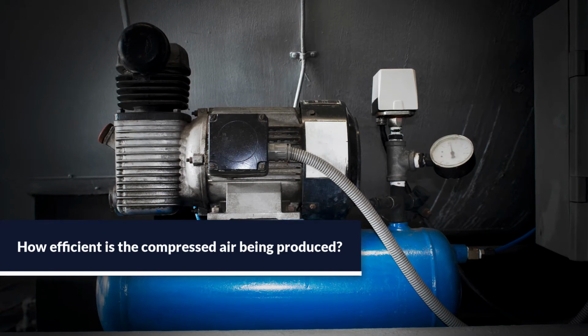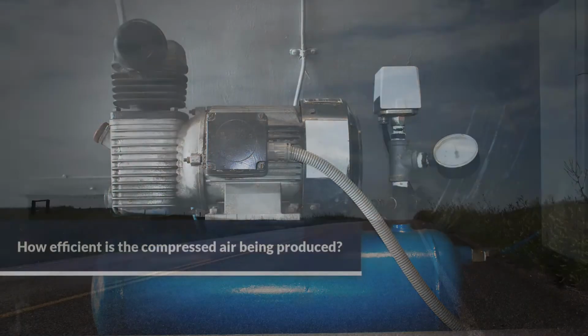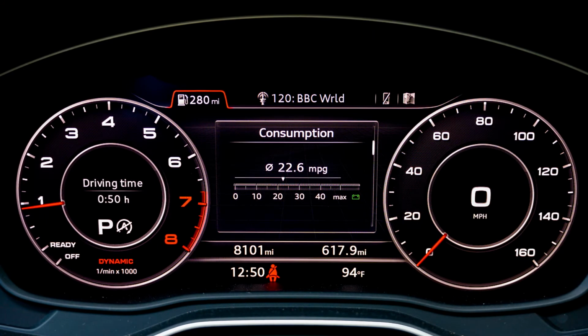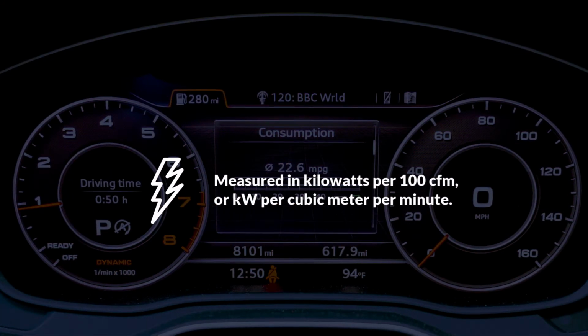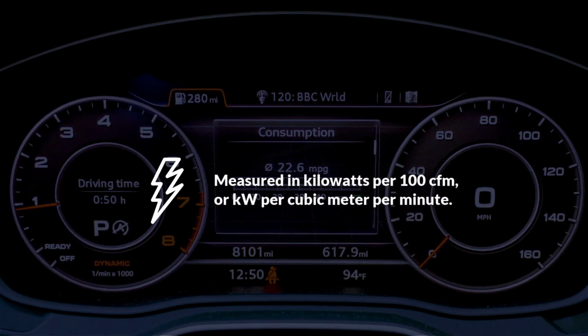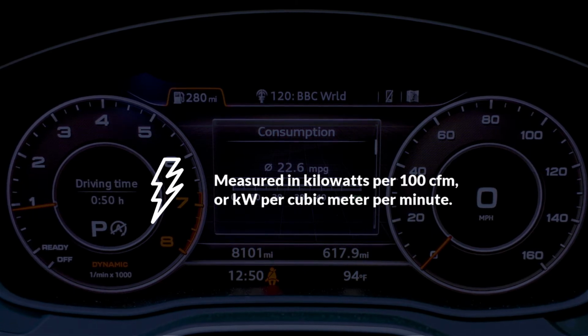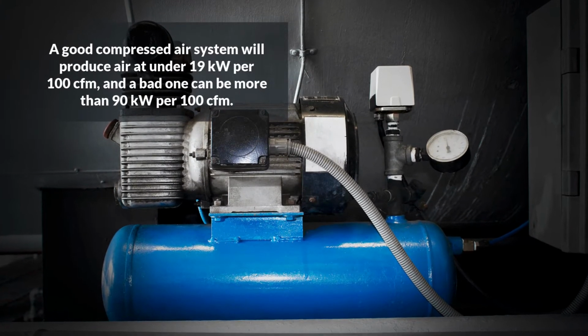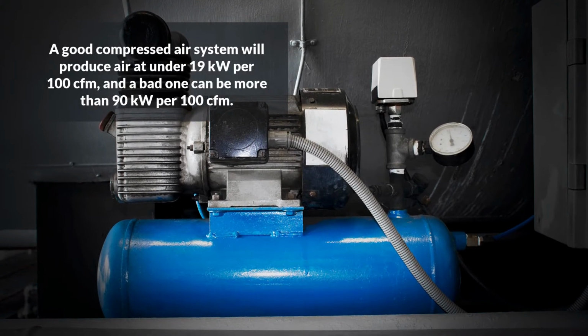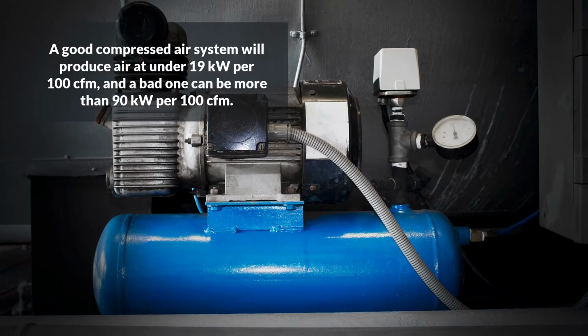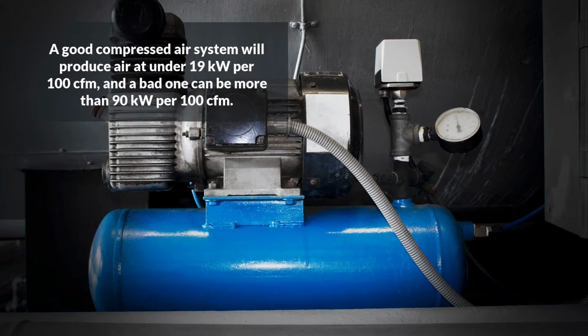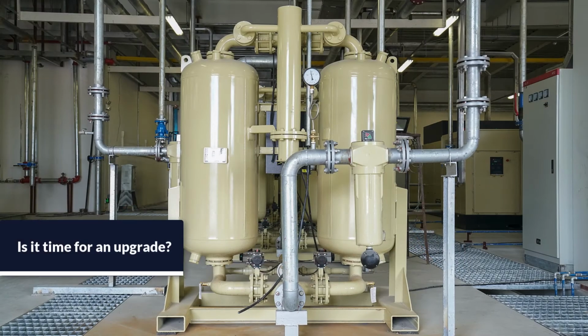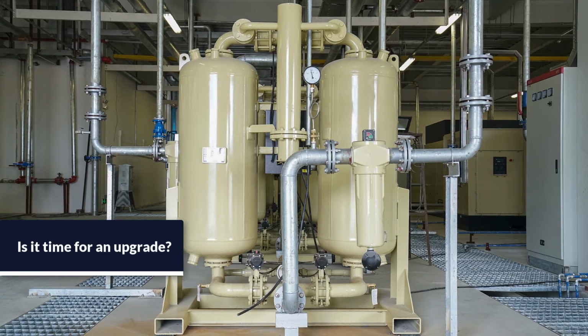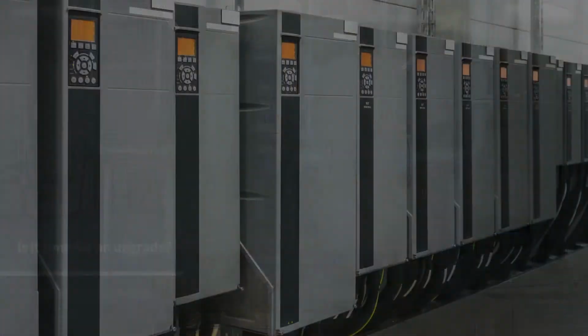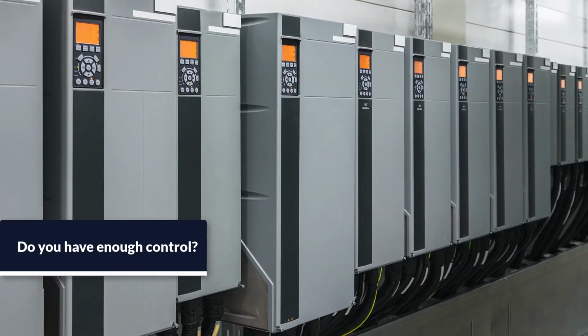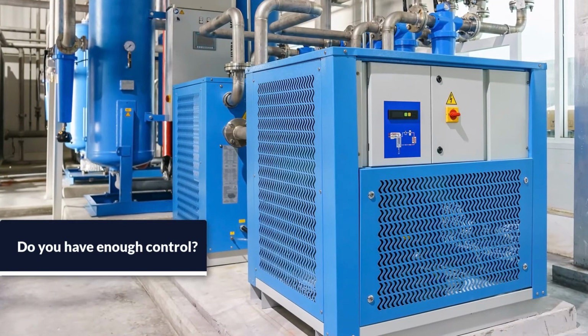System-specific power tells how efficiently the compressed air is being produced, much like a gas mileage indicator. This KPI is often measured in kilowatts per 100 CFM, or kilowatts per cubic meter per minute. A good compressed air system will produce air at under 19 kilowatts per 100 CFM, and a bad one can be more than 90 kilowatts per 100 CFM. Improvements to this measure can be gained by upgrading compressors to more efficient styles and by applying more efficient methods of control, such as variable frequency drives or cycling refrigerated air dryers.